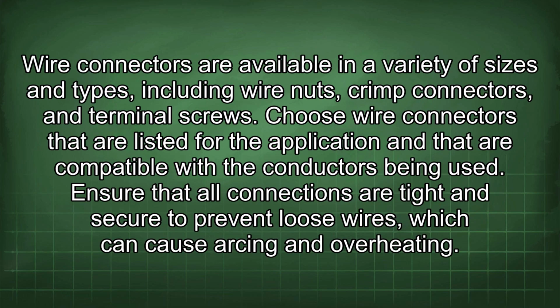Wire connectors are available in a variety of sizes and types, including wire nuts, crimp connectors, and terminal screws. Choose wire connectors that are listed for the application and that are compatible with the conductors being used. Ensure that all connections are tight and secure to prevent loose wires, which can cause arcing and overheating.